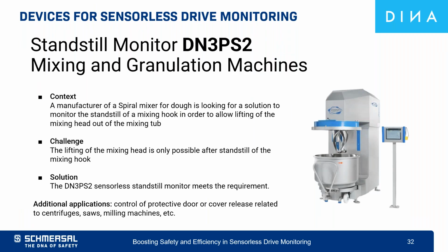And here I brought an example related to mixing and granulation machines. We have a customer who's producing spiral mixers. And as you can see here on the picture, there's a mixing tub, then the actual mixing hook, which is fixed to the mixing head. The challenge, or the task, was to control the lifting of this mixing head out of the mixing tub, so that it is only possible to lift the head out of the tub when the mixer or the mixing hook is at standstill. And in this case, the DN3PS2 fulfills all the requirements of this application. And yeah, also in this case, we made the customer happy.